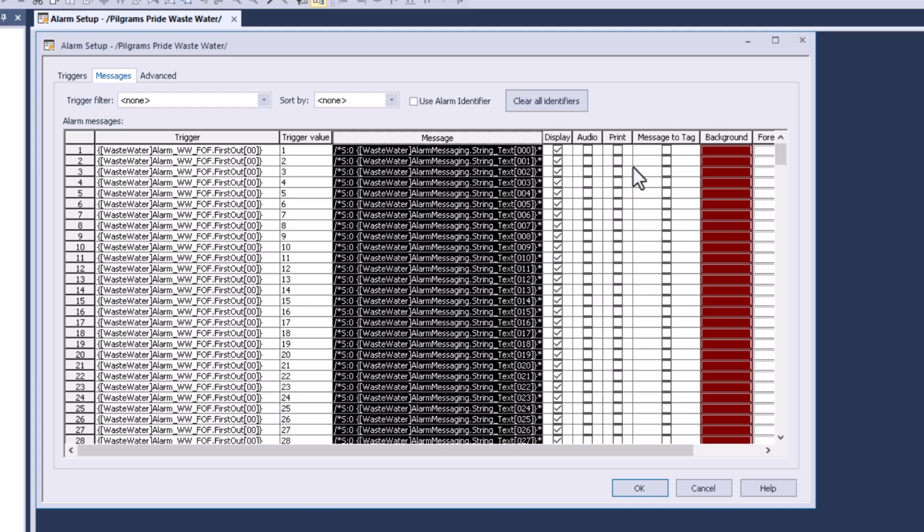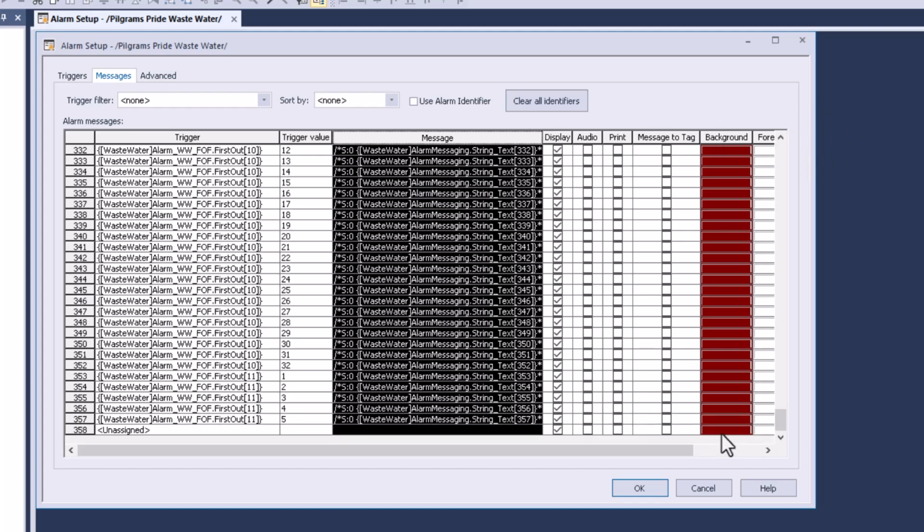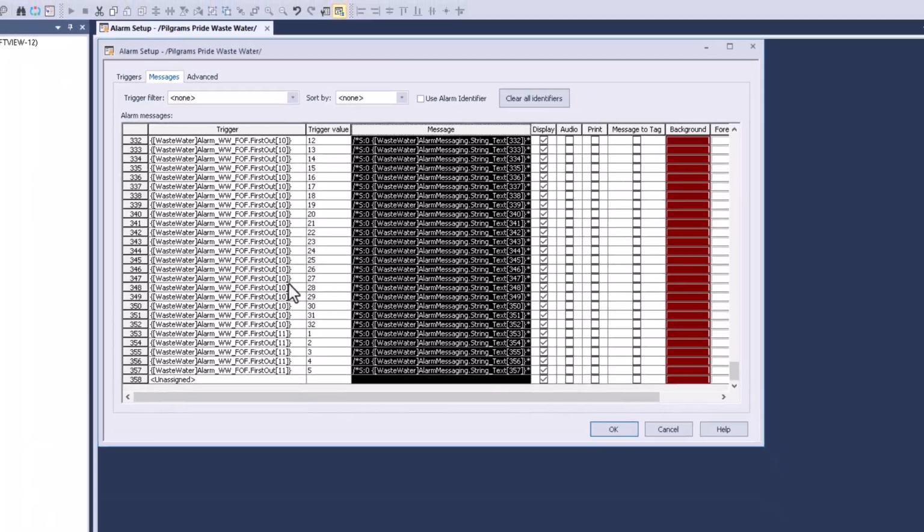So if you wanted to add an alarm, you can add an alarm. I always build in a lot more alarms than I'm going to use. That way the person behind me can always go in and add alarms, edit alarms, do whatever they want just via the PLC file instead of the actual HMI, right? So they don't have to constantly go back and edit the runtime and download the runtime to this panel view, this panel view, and this panel view. Say there's three of them being used, or if there's just one, it's not that bad, but it's still going to cost you about an hour, hour and a half, maybe 2 hours to do that work.